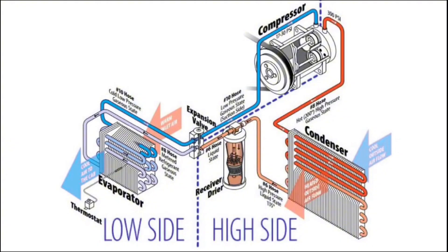Take a look at the color of the lines. The inlet of the compressor is always designated with blue to represent low pressure. After the compression process, the temperature goes high, so we give it the color red to represent the transition from lower to higher temperature. The blue-to-red color scheme also explains the pressure transition from low to high — for example, the vapor may enter the compressor at 17 to 30 psi and after compression becomes 300 psi. So the color representation shows which lines are hot and which are cold, and which are high-pressure versus low-pressure lines.